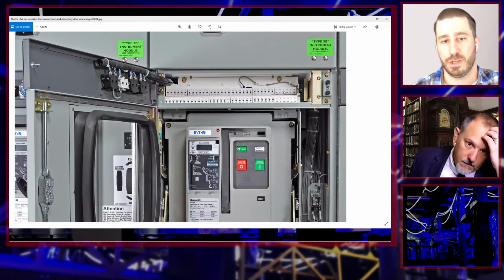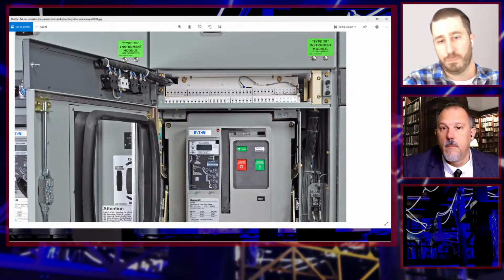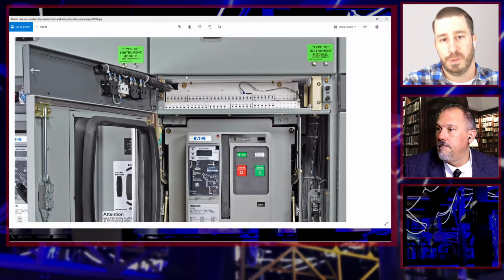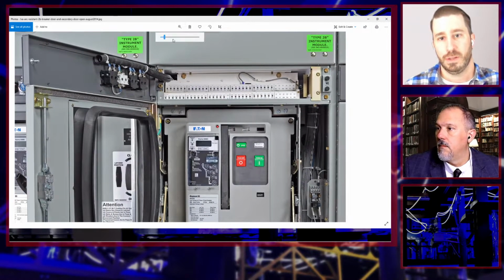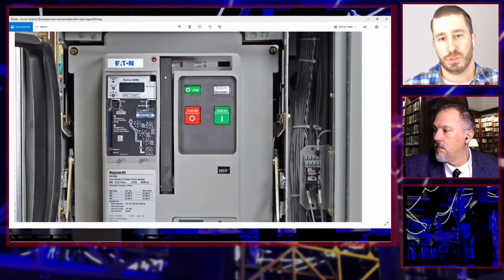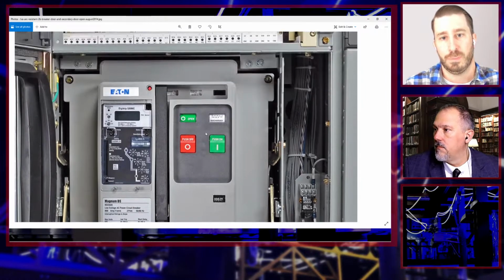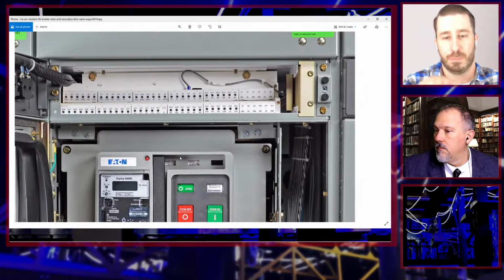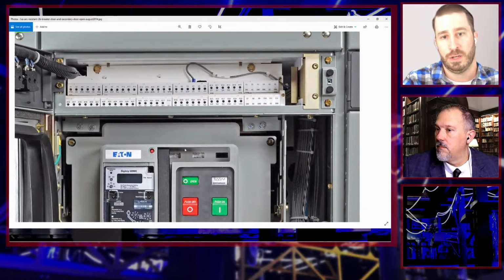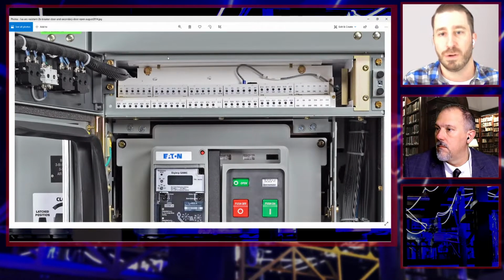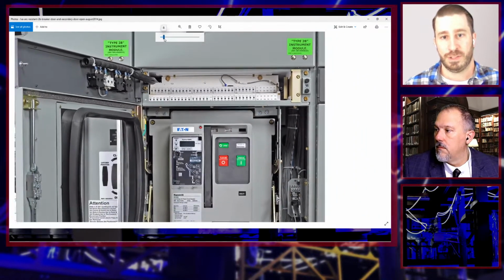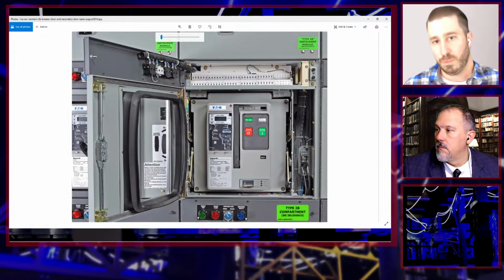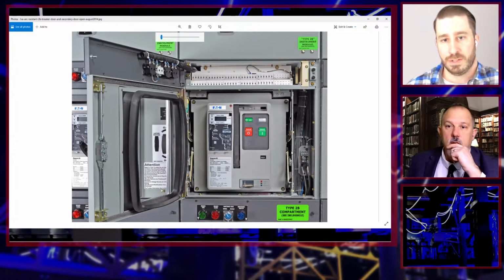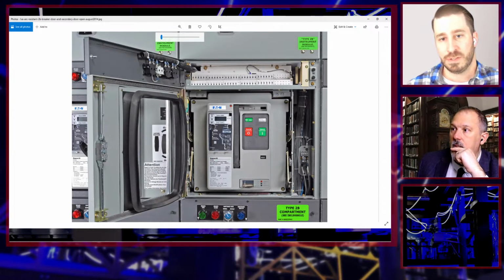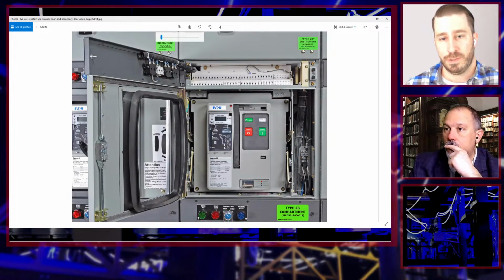So basically, assume that in this particular case, that main breaker door would be closed, but you've got some pilot devices in that compartment. That equipment would probably, if not usually, be tested without that control compartment door above. So that lower door would be shut, but that compartment up there — the difficulty is there's a great deal of control wire going from that breaker compartment into that control area. So you kind of have to effectively seal that off so that somebody could be working on that switch or pilot device or those contacts in that area, and that equipment is designed so that should an arcing fault occur in that breaker compartment, none of that is going to propagate into that area.